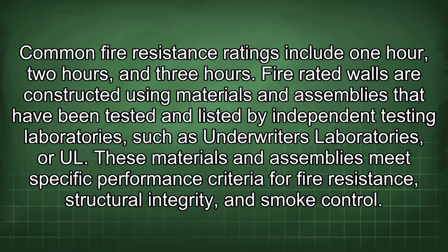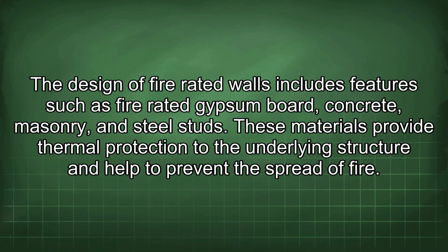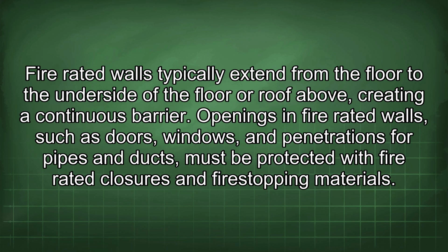Fire-rated walls are constructed using materials and assemblies that have been tested and listed by independent testing laboratories such as Underwriters Laboratories or UL. These materials and assemblies meet specific performance criteria for fire resistance, structural integrity, and smoke control. The design of fire-rated walls includes features such as fire-rated gypsum board, concrete, masonry, and steel studs. These materials provide thermal protection to the underlying structure and help to prevent the spread of fire. Fire-rated walls typically extend from the floor to the underside of the floor or roof above, creating a continuous barrier.